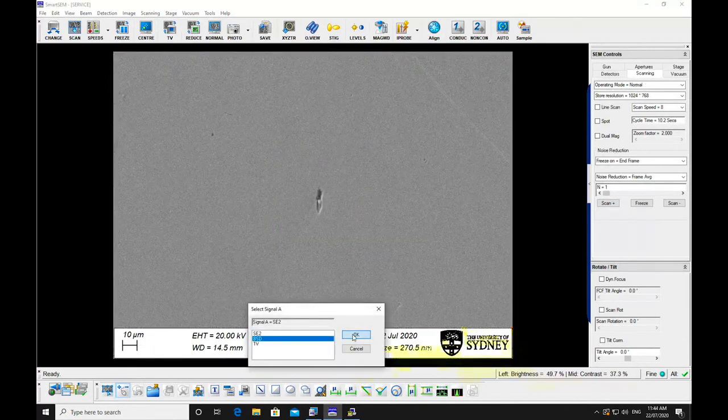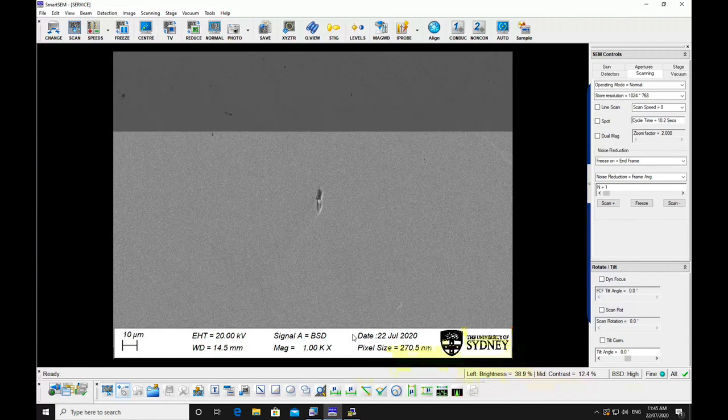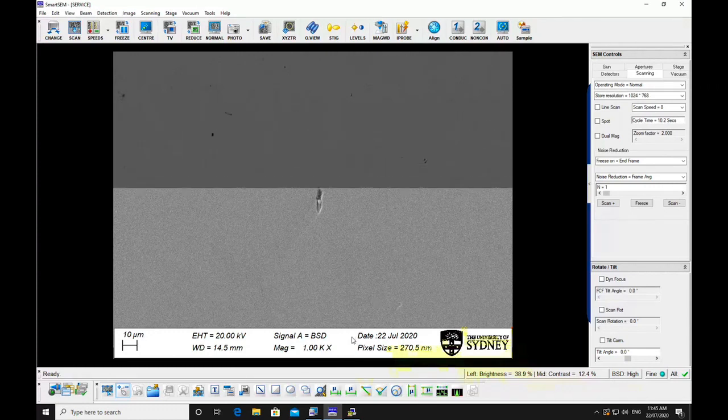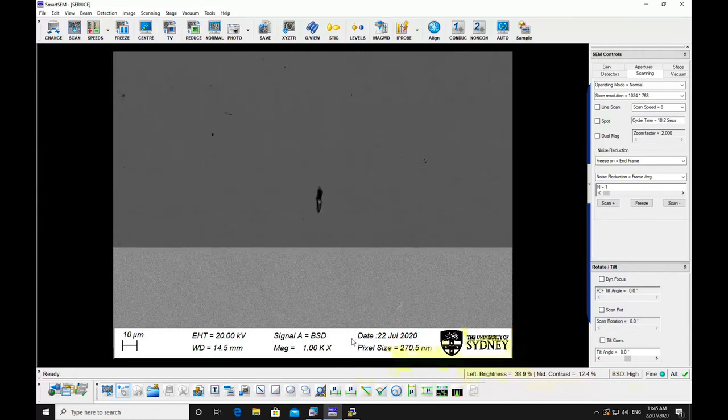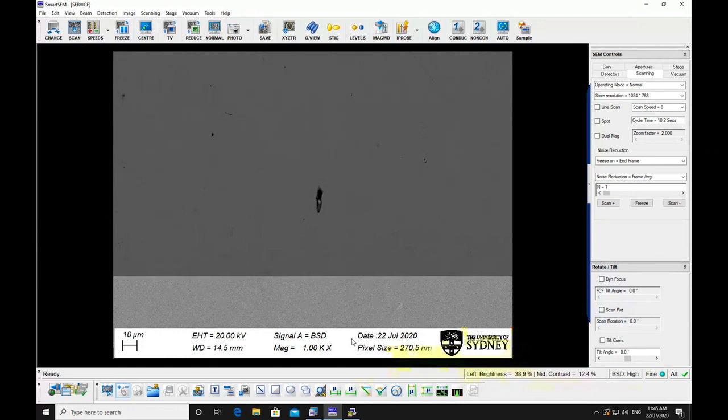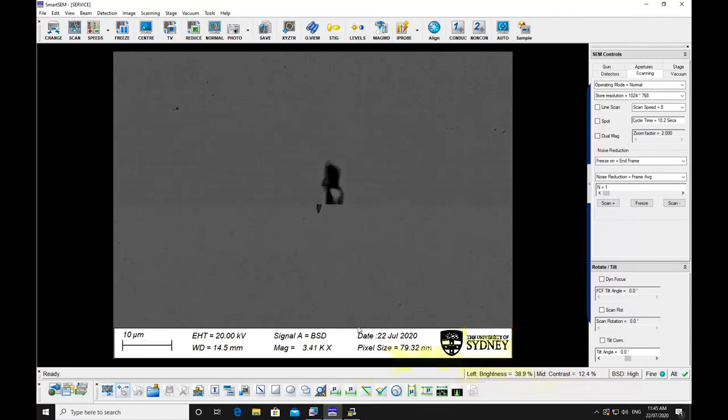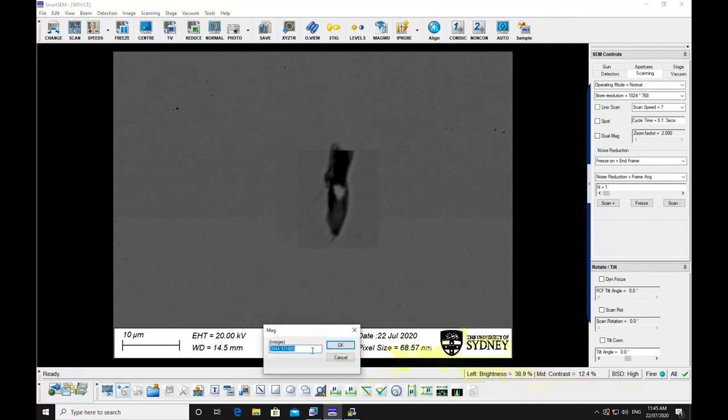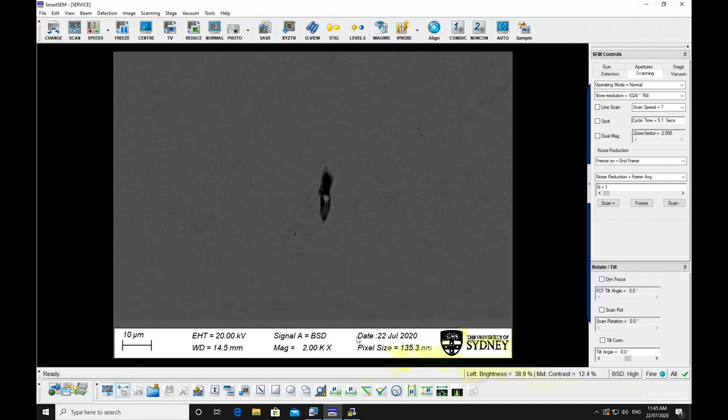Select the detector you require, either SE2 for topographic or BSD for compositional imaging. Focus and stigmate the image at 2 to 4 times the magnification you want to capture the image. Adjust the brightness and contrast so that the maximum detail can be seen in the image.